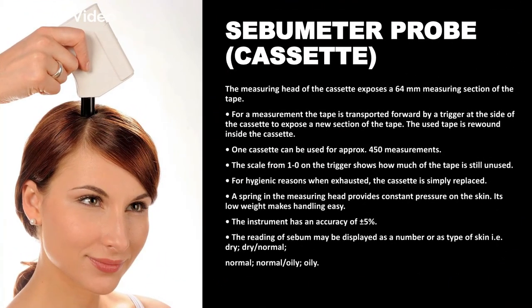This is the equipment being discussed. The black color part is known as the cassette. The measuring head of the cassette exposes a 64 mm measuring section of the tape; a trigger at the side of the cassette transports the tape forward to expose a new section. Inside the cassette, a tape runs and rewinds. One cassette is approximately used for 450 measurements. The scale from one to zero on the trigger shows how much of the tape is still unused. For hygiene reasons, when exhausted, the cassette is simply replaced. A spring in the measuring head provides constant pressure on the skin. The instrument has an accuracy of plus or minus 5%.